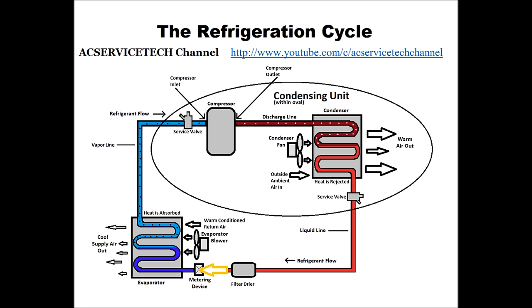After it goes through the thermostatic expansion valve, the molecules are all spread out and the temperature becomes much, much lower. A very easy way of remembering what superheat is: it's the temperature increase in vapor form in the evaporator coil. There's only one spot where there's vapor in the evaporator coil — it's after the saturated state. We typically take our temperature and pressure reading right after it gets out of the evaporator coil, or as total superheat out at the compressor.